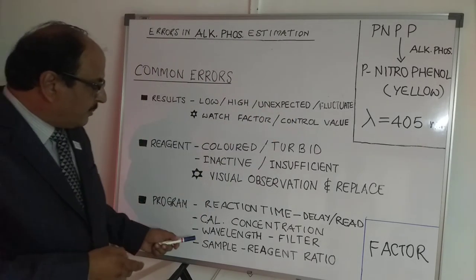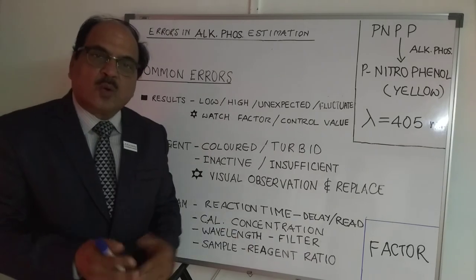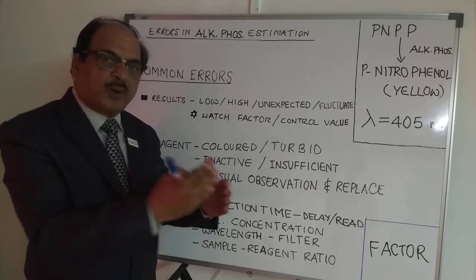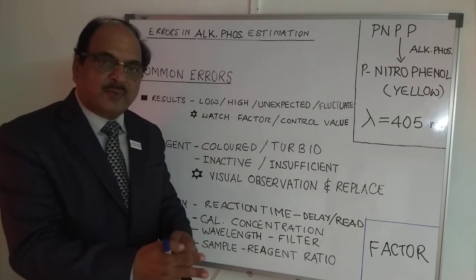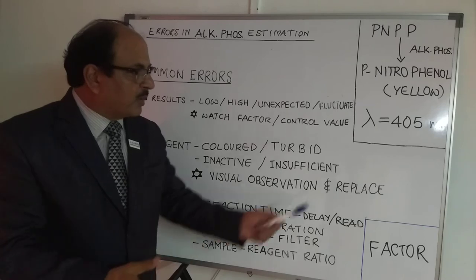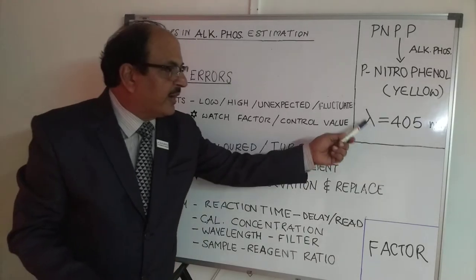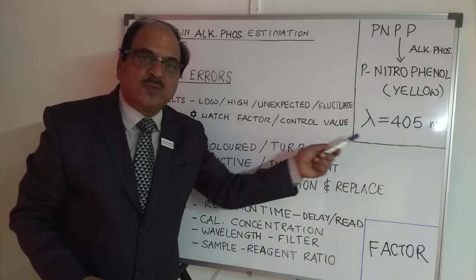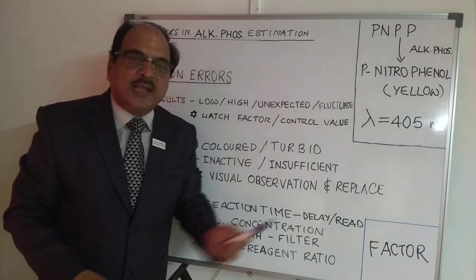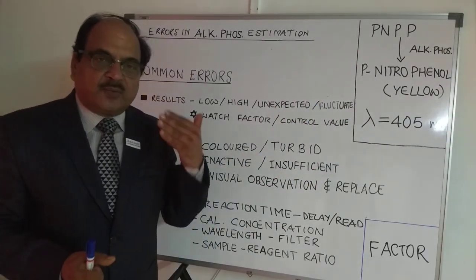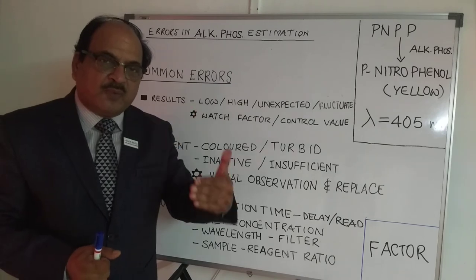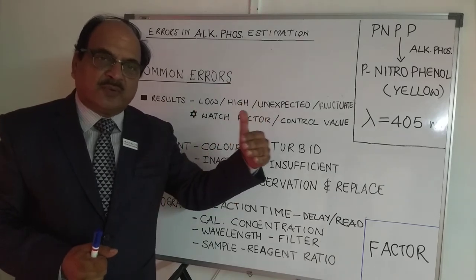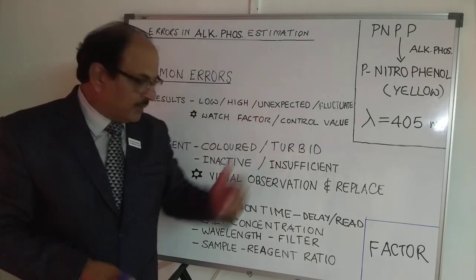Next is wavelength. Commonly, when you copy one program to a second program during programming, you tend to forget to change the wavelength to 405 nanometers. Ensure that your program has a 405 nanometer wavelength set correctly.